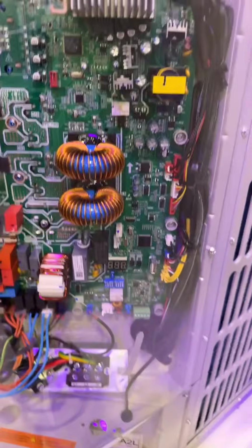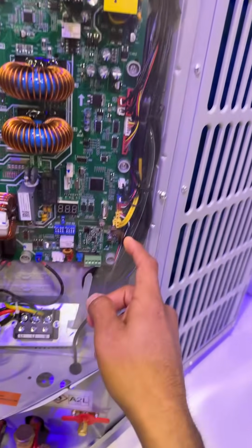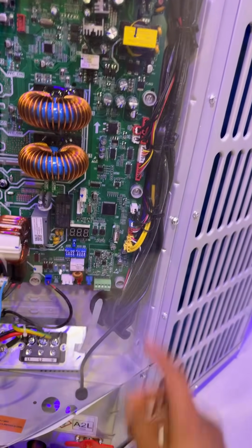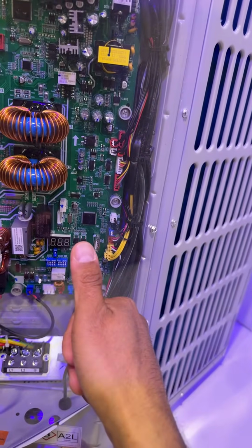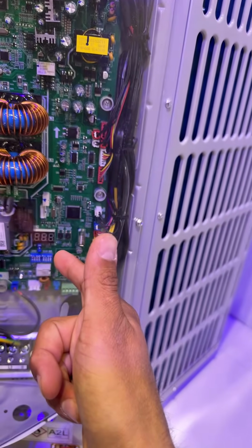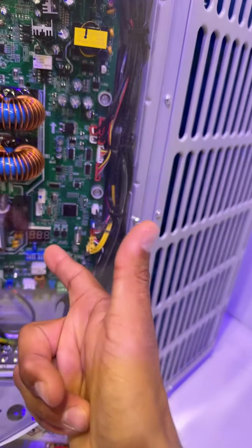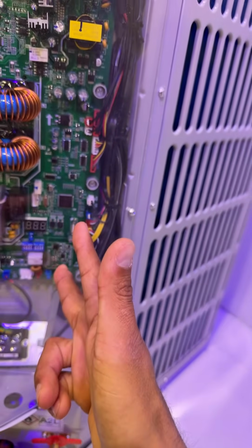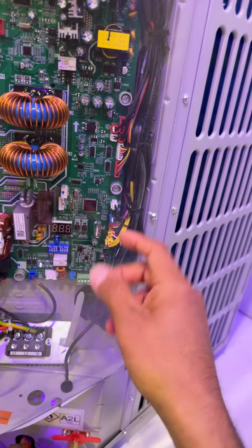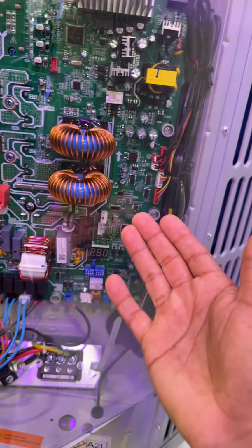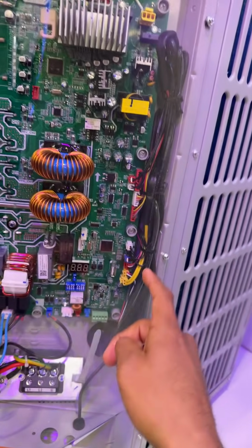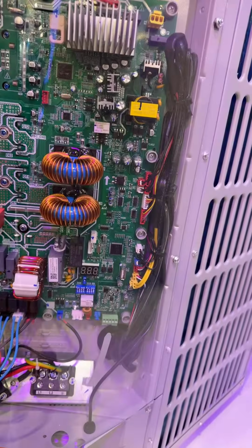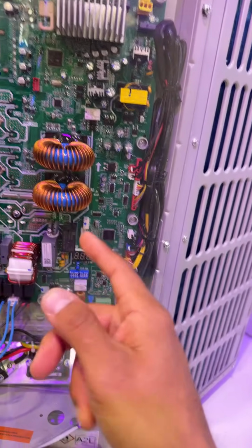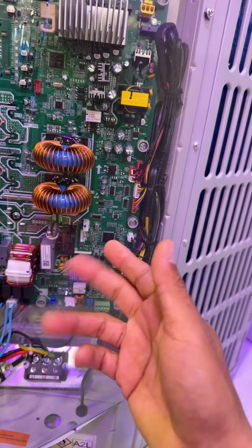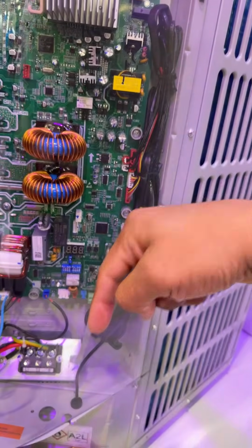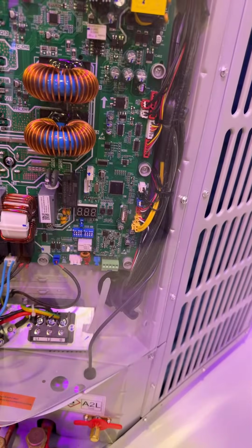One last thing and I'll have to let you guys go. But let's talk about how it works. You got different thermistors everywhere that read temperature. So you have a discharge line, you have a discharge line temperature sensor, a temperature sensor on your indoor coil, on your outdoor coil. You have one for your outside air temperature, and you got other temperature sensors. But the way they work, these thermistors you see, they're reading temperature. So let's say your outside air temperature starts to pick up, it communicates with your PCB, and your outdoor fan ramps up even more to reject more heat. Let's say that your suction pressure goes up, and your compressor will ramp up to bring the suction pressure down. So that's all we're doing with the technology. It's pretty cool, I really like it.